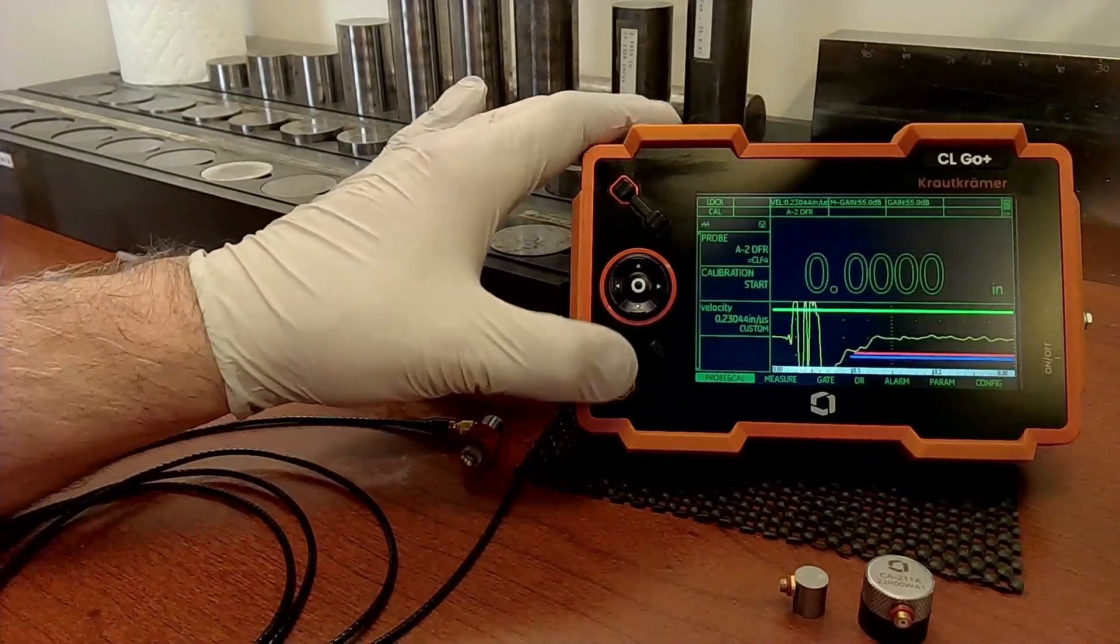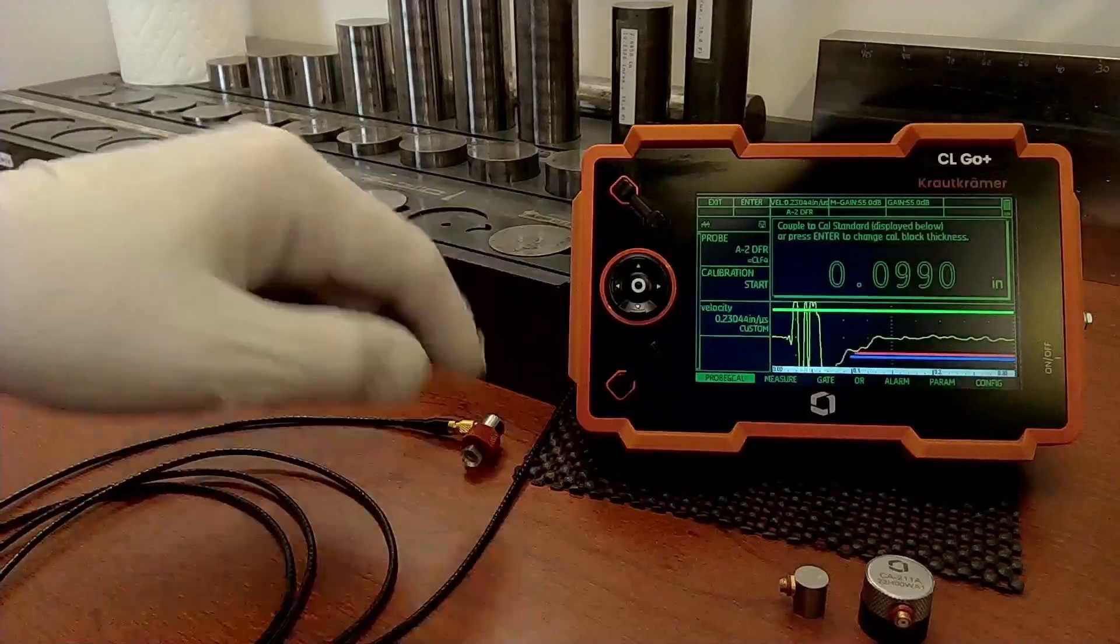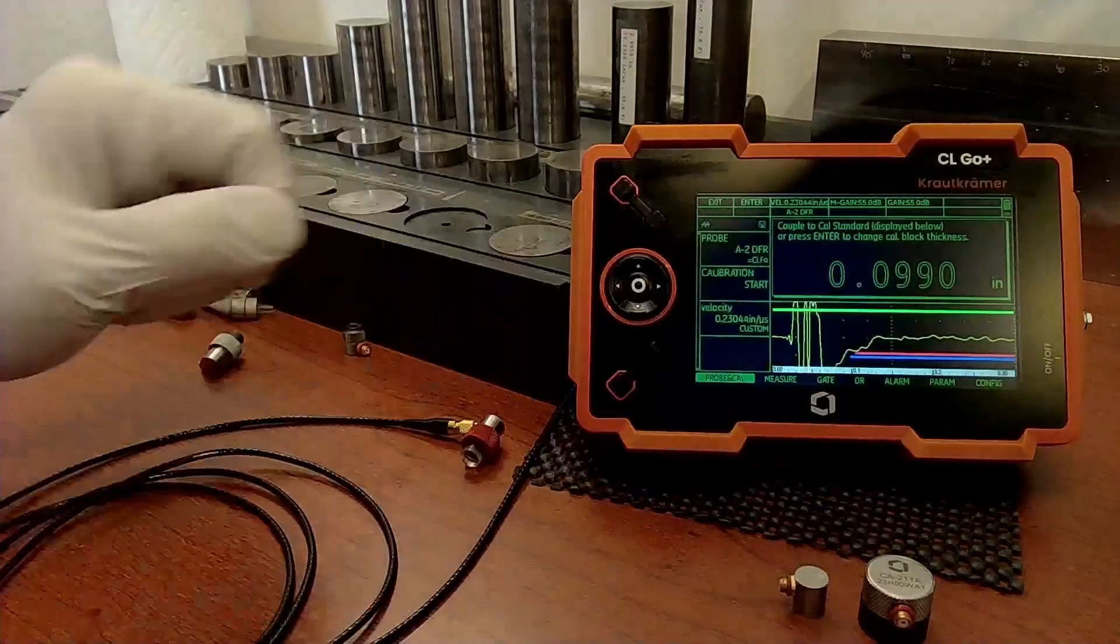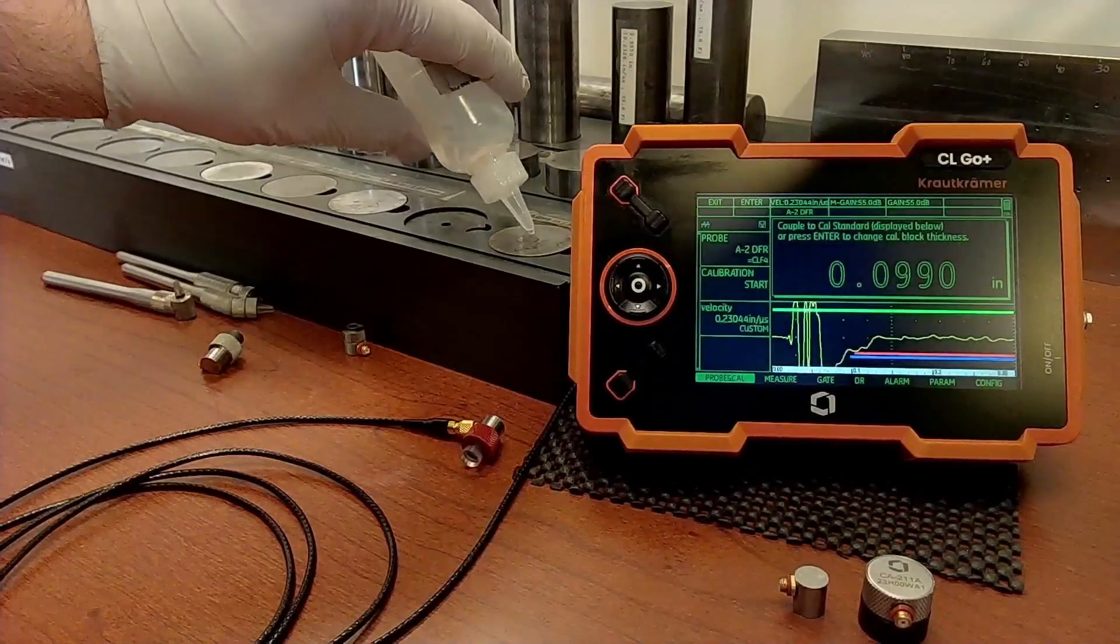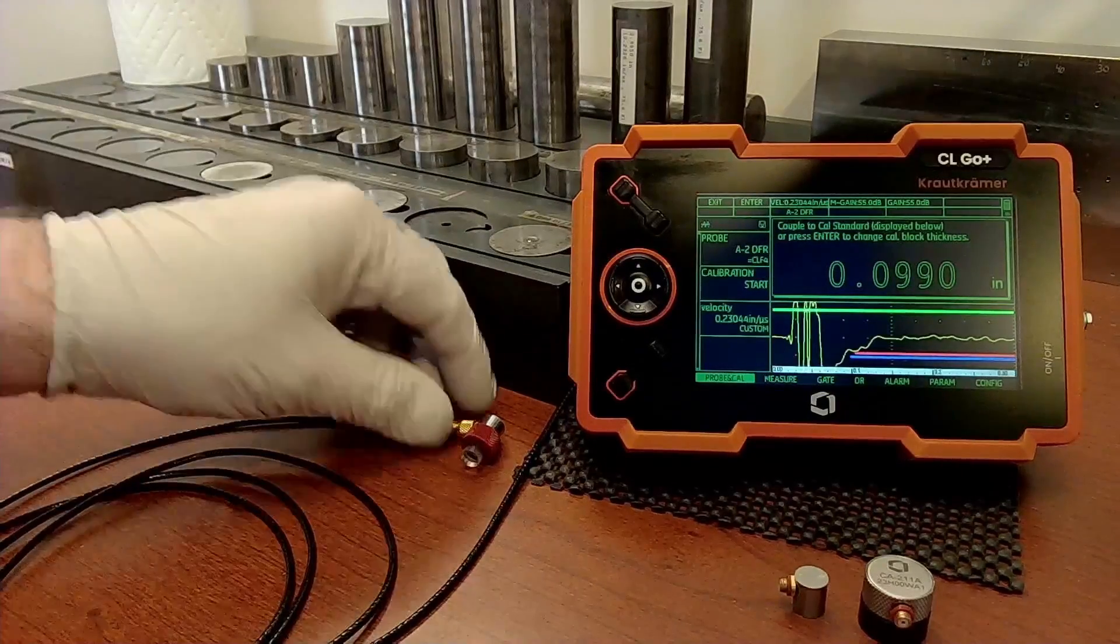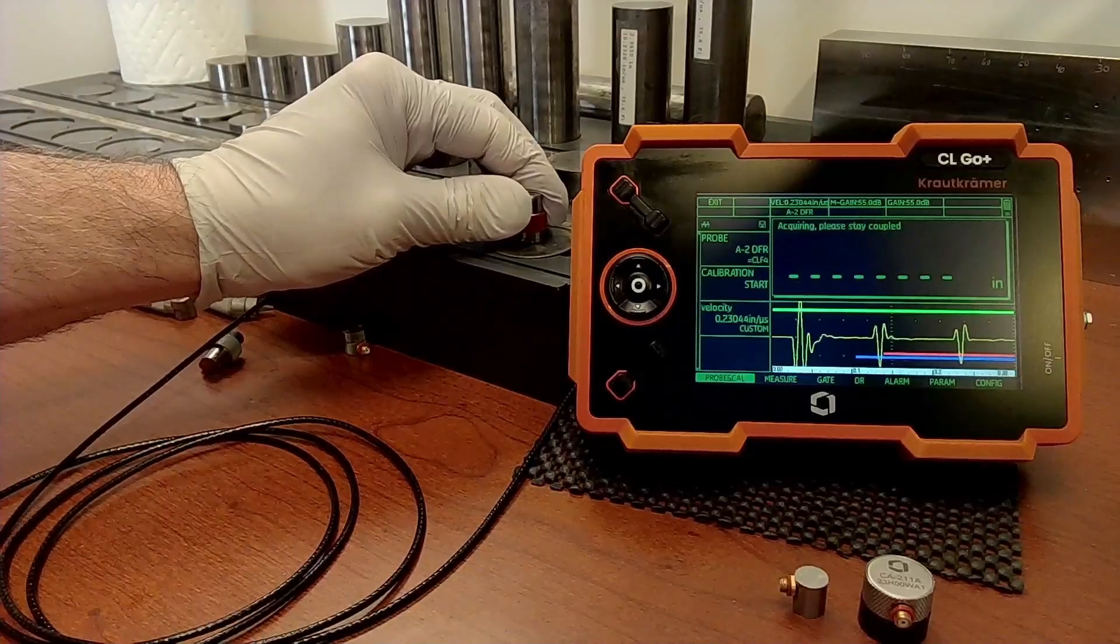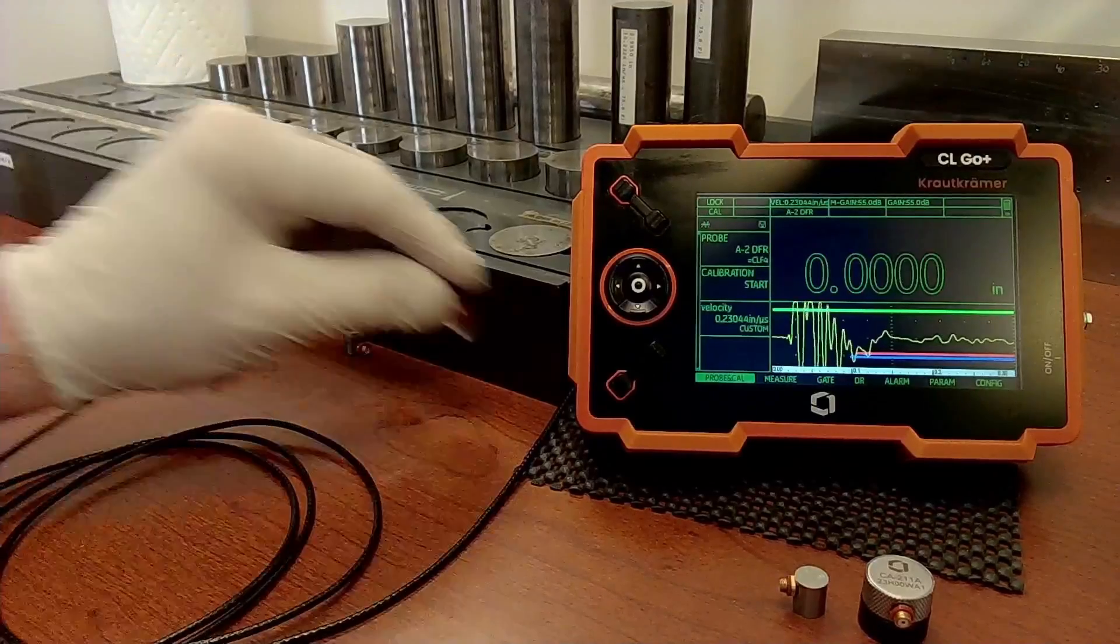We're powered up. I hit the calibrate button. Now I've previously told it that my calibration standard is 99 thousandths of an inch thick. Put a drop of couplant back here on the 99 thousandths block. Couple up. The instrument says go ahead and take the probe off.